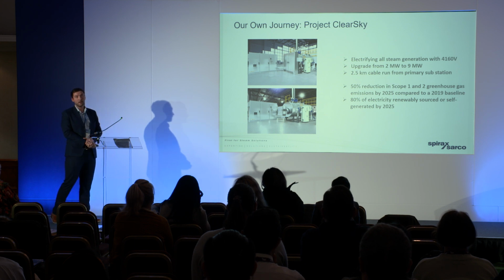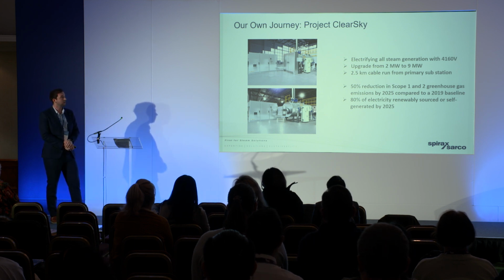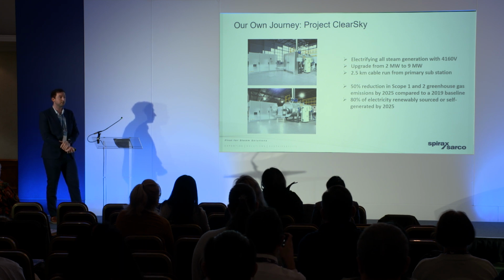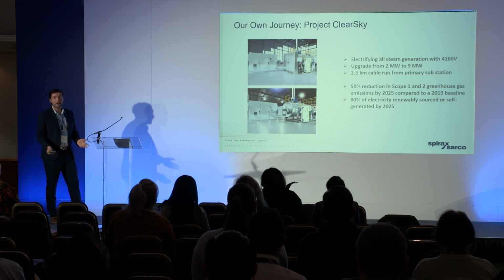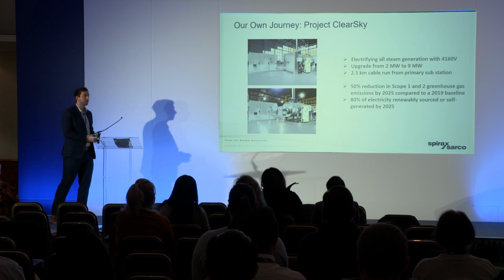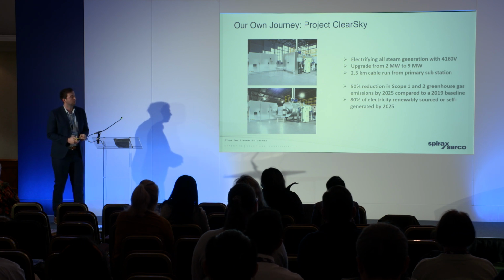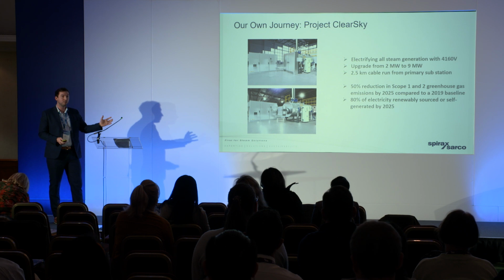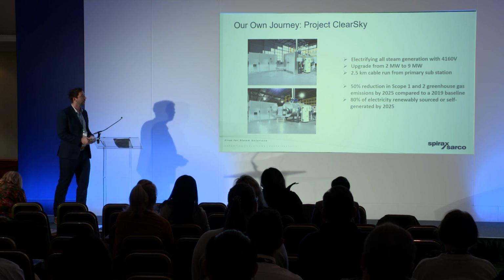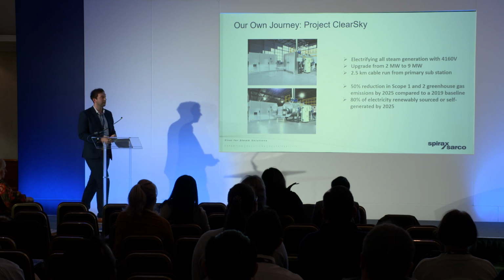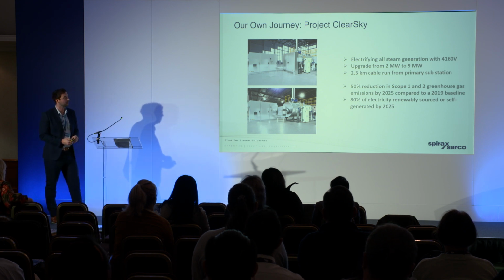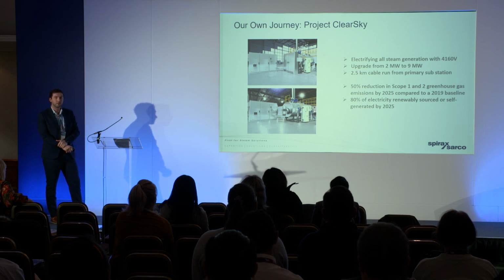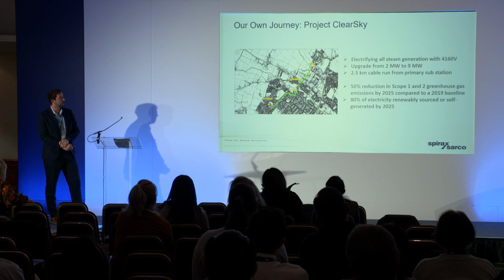And we're walking the talk as well. At our largest manufacturing facility in Cheltenham, we've made the decision to electrify our entire steam generation, so swapping from gas to electricity. We're doing it at a high voltage, 4,160 volts, to enable us to reduce the current, which reduces our losses. We're upgrading from 2 megawatts to 9 megawatts. We've actually run all the power into the site now, a 7 megawatt increase, 2.5 kilometre cable run, which made us very unpopular with the locals. But it's the right thing to do to decarbonise our site. So we're targeting that 50% reduction in Scope 1 and Scope 2 by 2025, and 80% of our electricity will be self-generated or renewably sourced. And there's a map of Cheltenham where we've run our cable.